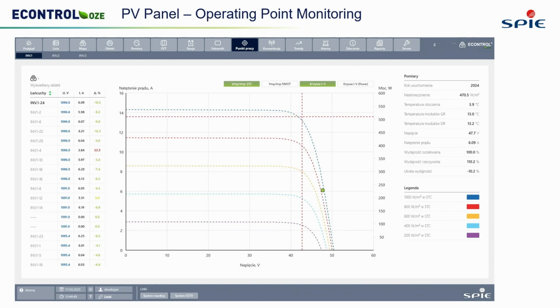The nice thing is operating point monitoring, because in our system we take data from the panel producer on the characteristic aging of those panels. We know the panel produces less each year than at the beginning. By using this characteristic, we can trace the production level, compare it, and if there's too much deviation in our opinion, we can contact the producer and ask what happened, since it should be producing more.